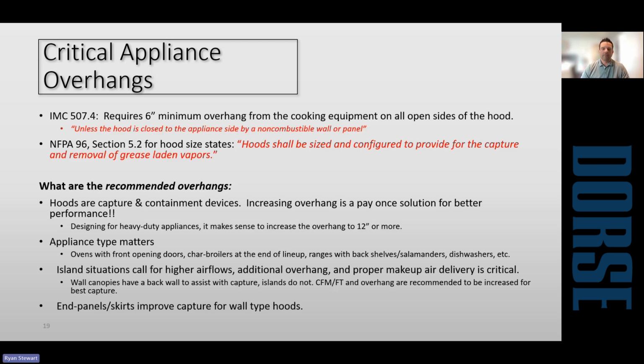So what I tell people when I look at jobs is, if you think about making a hood 12 inches wider or deeper, it's really only 4 square feet of sheet metal. So it's a pretty minimal cost up front to have major benefits for the life of the system. When you're looking at appliance layouts, if you have real heavy duty cooking appliances out on the ends of the line, that's where you want to push to have 12 or more inches of overhang and not just go with the minimums. Appliance type matters.